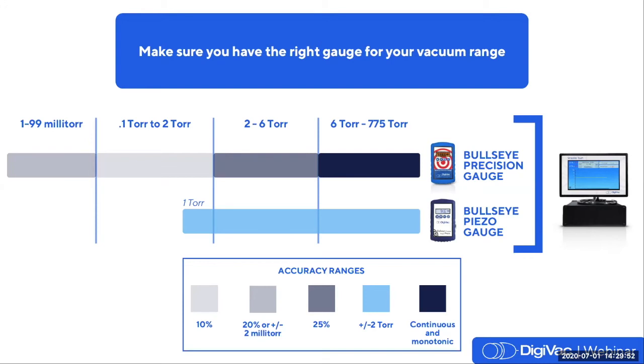Now, our bullseye piezo gauge is not a thermocouple instrument at all. So it excels in a totally different area. The piezo-resistive sensor is isolated and reads from 1 torr to 775 torr. So we get nothing out of this particular gauge and sensor below 1 torr, but from 1 torr to 775 torr, we call our accuracy range plus or minus 2 torr. So that's great accuracy all over a more limited range.